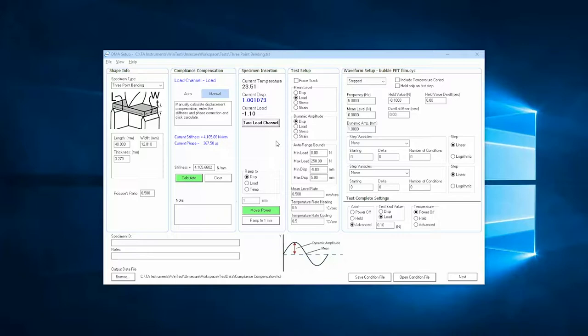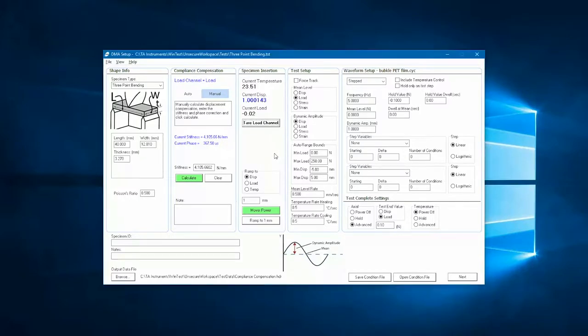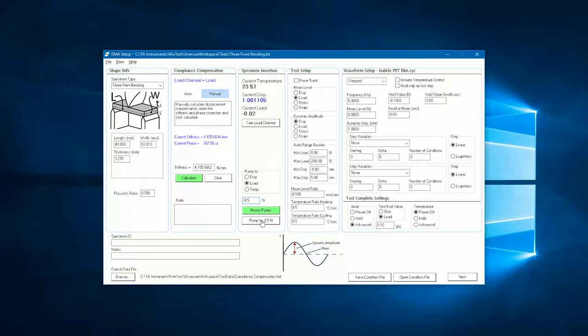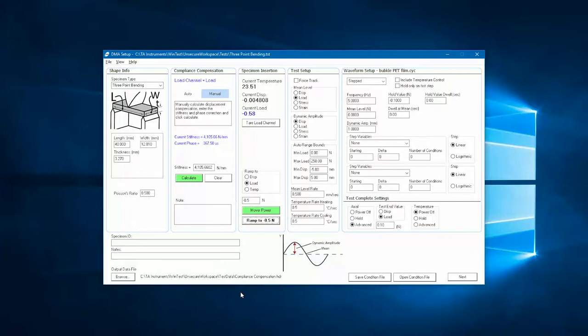To command a desired displacement, load, or temperature, we can use the radio buttons in this section. Manually type the desired value and click the ramp to button. This will engage the adaptive controller and bring the actuator to the desired position, load value, or temperature. The motor power button is also located within this section.